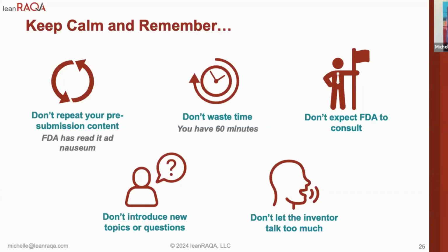And then don't let the inventor talk too much. If your inventor insists on being at the meeting, again, I mentioned something earlier about being in love with your own science, and that can derail a conversation with the FDA, because these are supposed to be very pointed follow-up questions and topics specifically related to information that you have already provided and responses that they've already given.